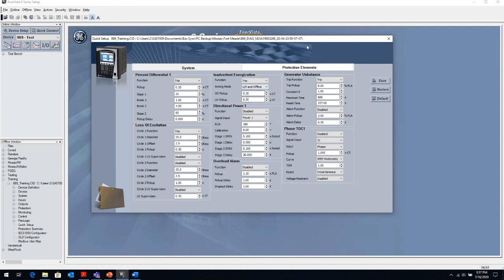Then I also have the generator unbalanced protection enabled. This is again percent of full load rating. And there's some time settings. In this case, this is very long. So there's something I'm coordinating with that has a very, very long time delay that's out of my system. And then my various other elements. So these are the most common and basic elements that we would use for an industrial generator protection.